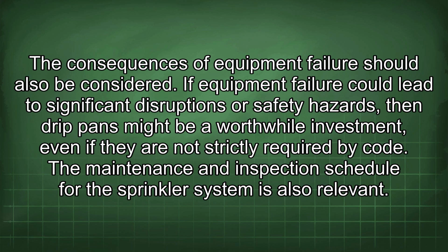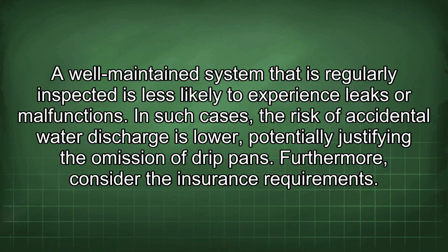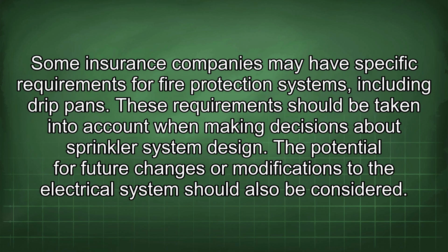The maintenance and inspection schedule for the sprinkler system is also relevant. A well-maintained system that is regularly inspected is less likely to experience leaks or malfunctions. In such cases, the risk of accidental water discharge is lower, potentially justifying the omission of drip pans. Furthermore, consider the insurance requirements. Some insurance companies may have specific requirements for fire protection systems, including drip pans. These requirements should be taken into account when making decisions about sprinkler system design.